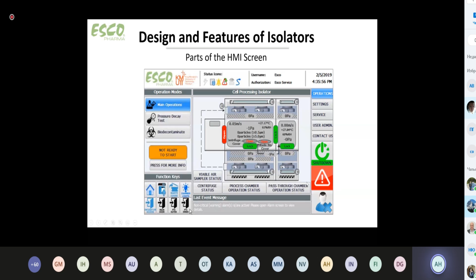This would be a sample of how you check for your reports, your records, your printer setting, and your audit trail. So this here basically allows you to enable or disable your onboard printer. It will log a lot of information like all your data, your alarms, and your audit trail. And you can set the directory of the logs where you want to save it. You can even transfer this to a USB. You can transfer this to the building management system. And you can change the frequency of log, every minute, every 10 minutes. You can configure a lot of this.